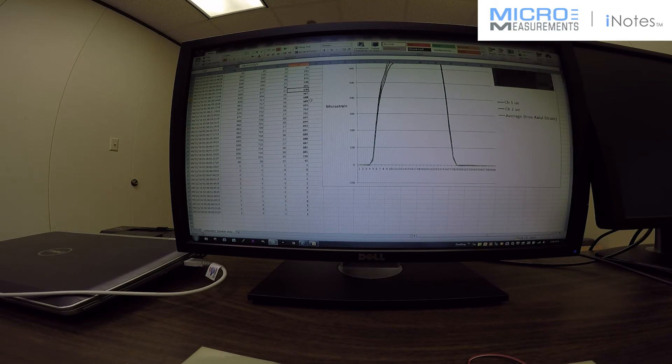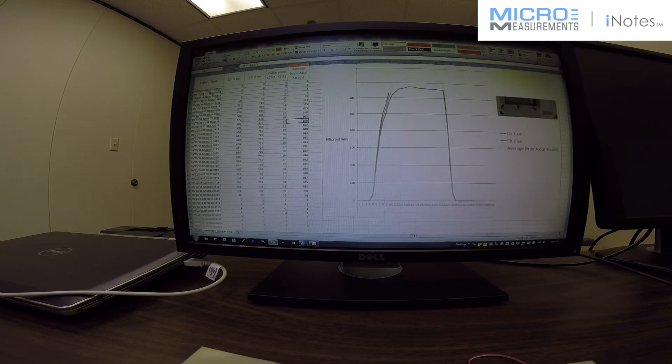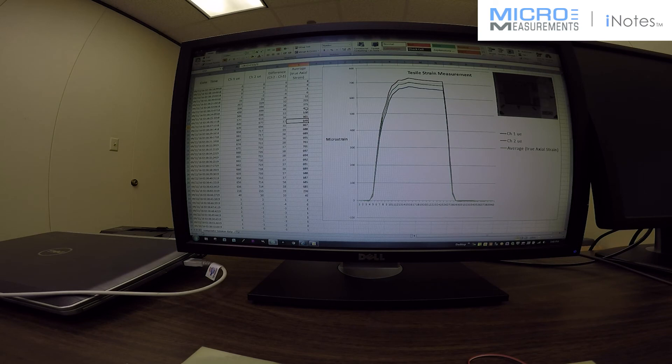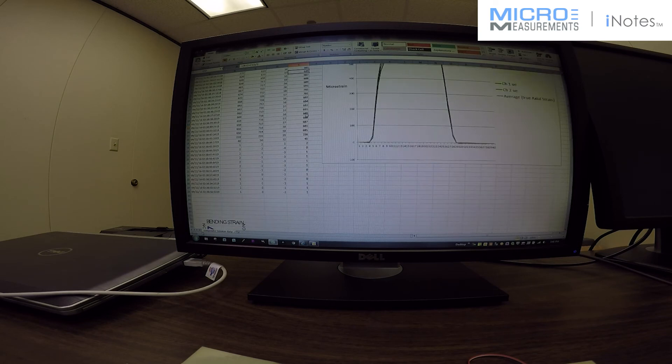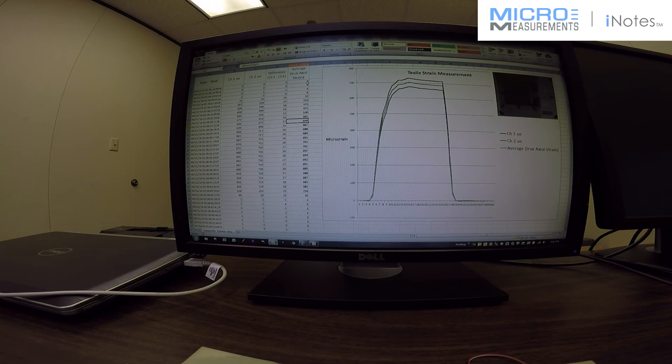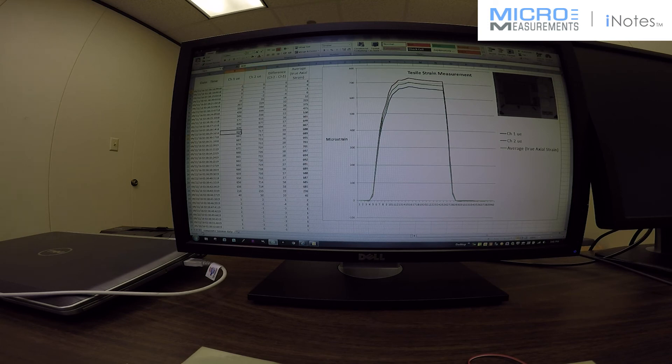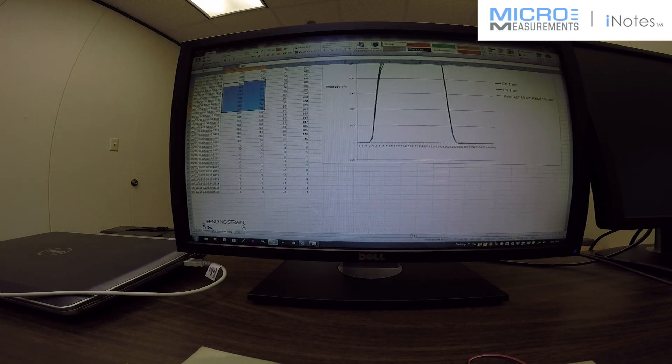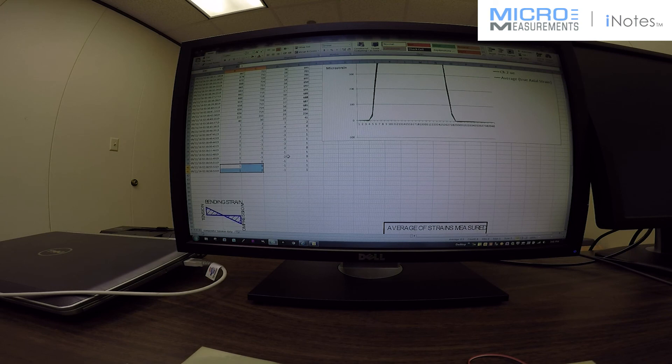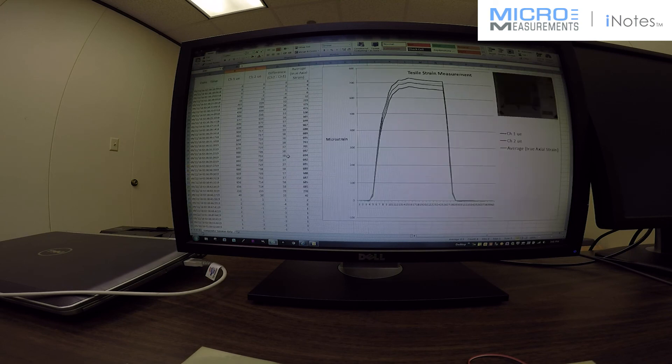Now one other important point I will show you here regarding any strain measurement: a lot of times customers will call us and say, well, how do I know if my strain gauge worked throughout the test? And it's actually obvious here. This is why I'll point it out. You can see that at the start of the test both strain gauges were initially zeroed, and then we loaded it to several hundred microstrain, and then I unloaded it. And you know, aside from a little bit of weight of the fixture, they both went back to zero. This is an indication that the strain gauges gave me good data all the way through the test.